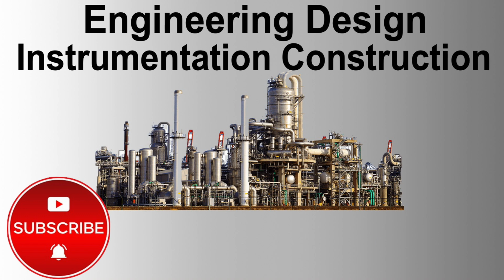Some level instruments are susceptible to damage due to vibration. To minimize effects of vibration, they should be installed on a rigid support. If this arrangement is employed, tubing and conduit connections should be installed to allow for movement. Where turbulence caused by emptying and filling rates or by mechanical agitation can affect the sensor, it is necessary to enclose the element in a stilling well.